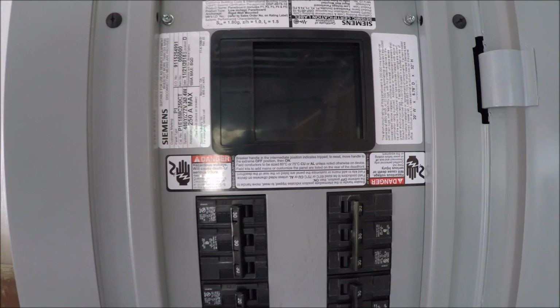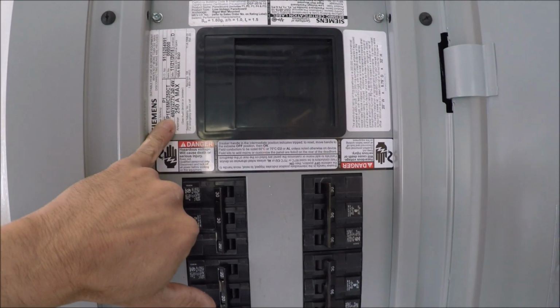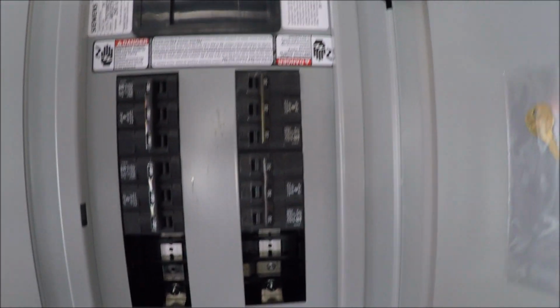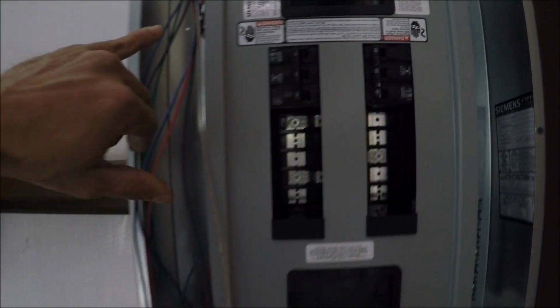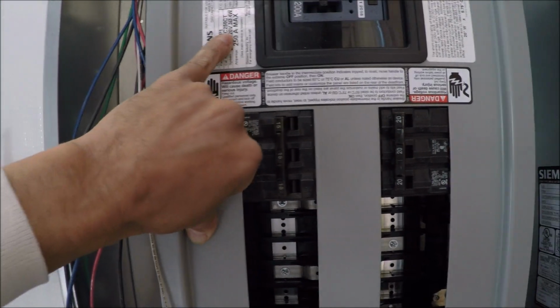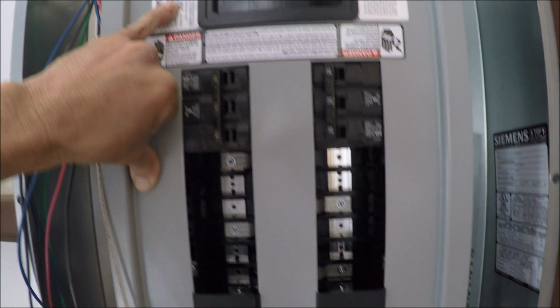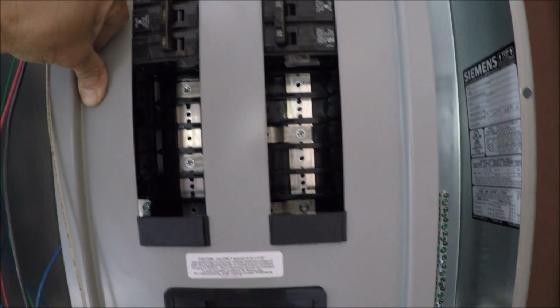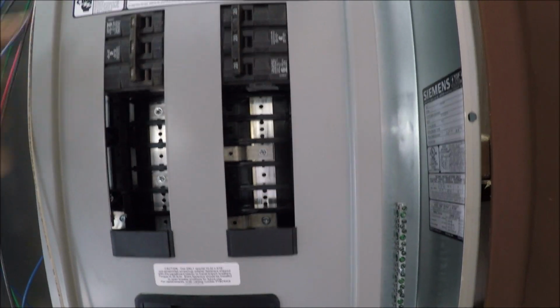And here's the specs on the 480-277. This is for the high voltage side. So we'll split it, one for the heavy machines, and then over here you can see it's 208 120. So the 120 is going to power the offices, all of the small stuff.